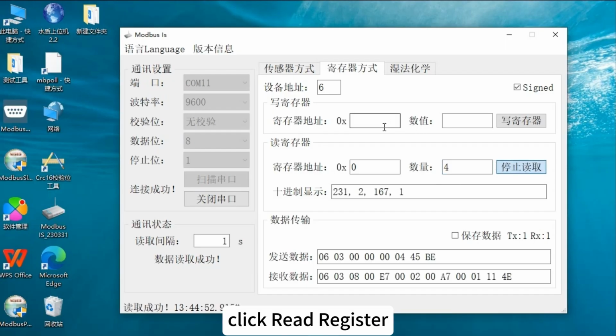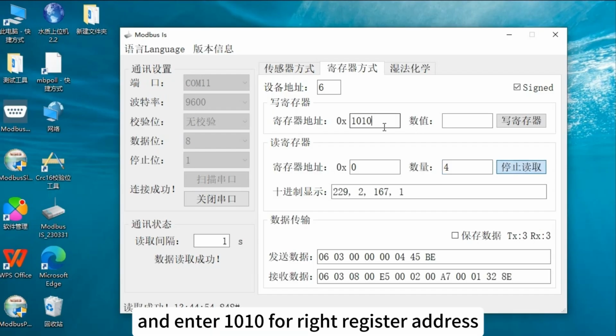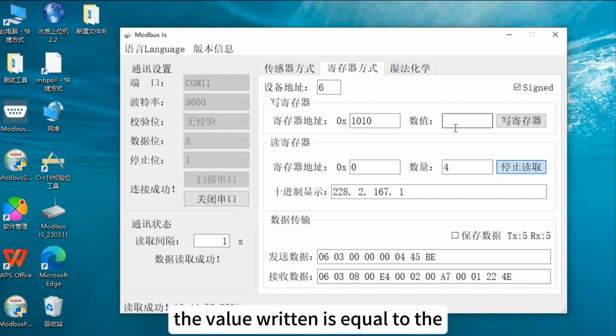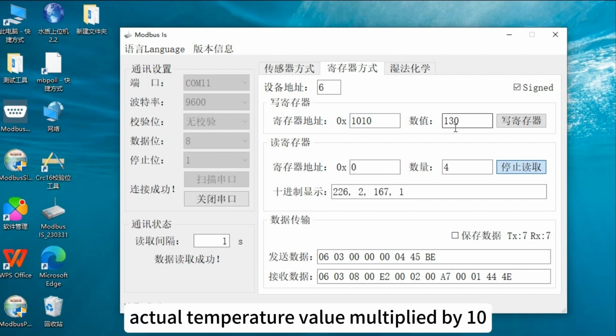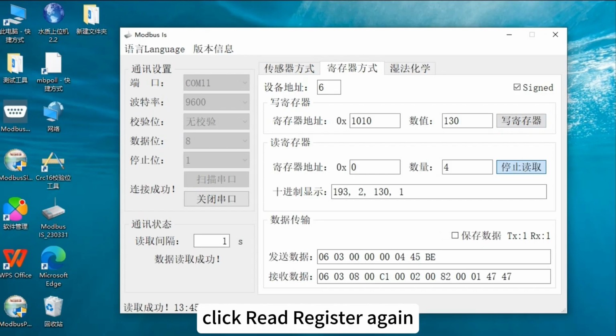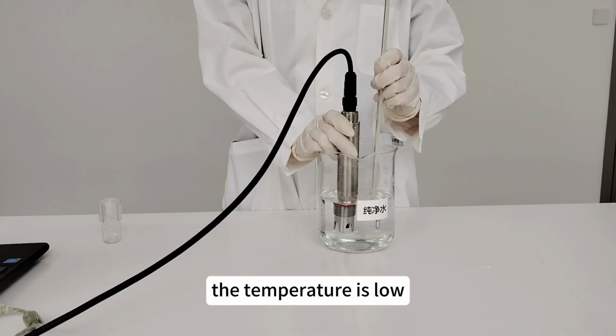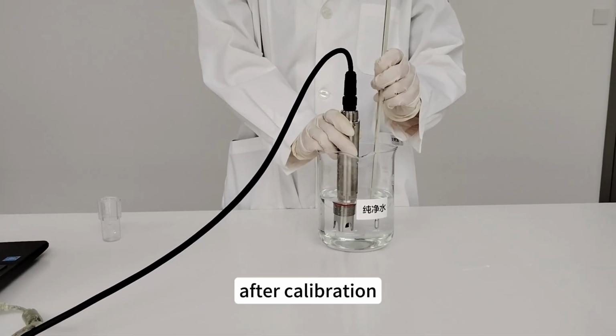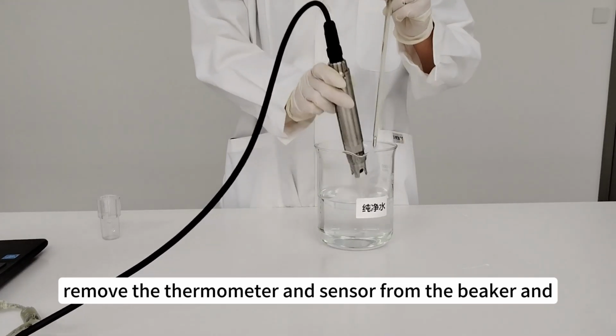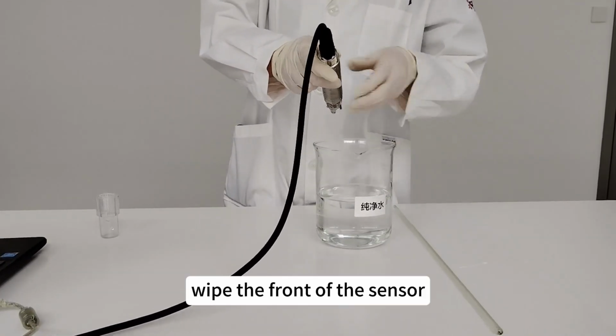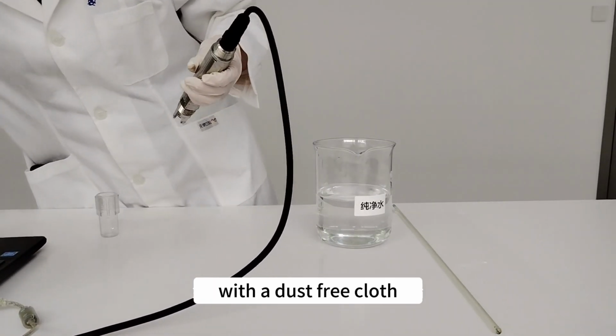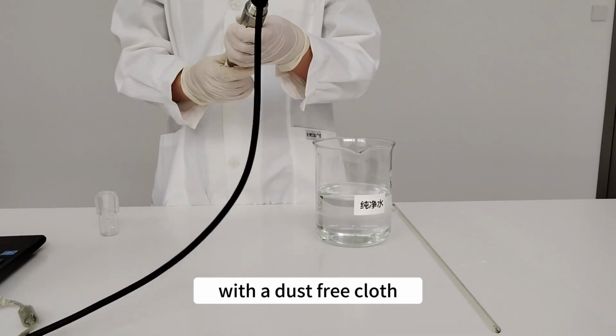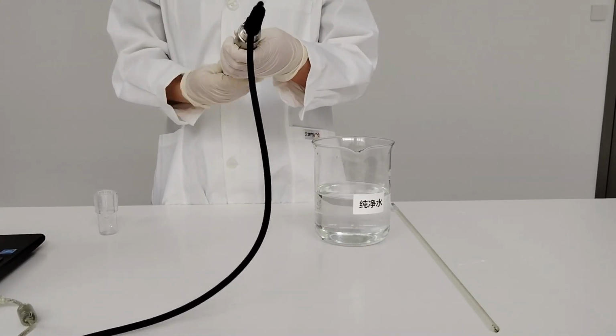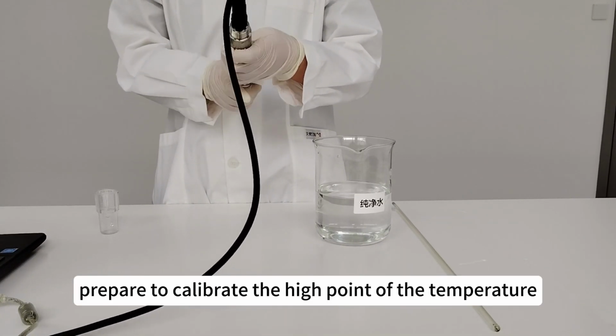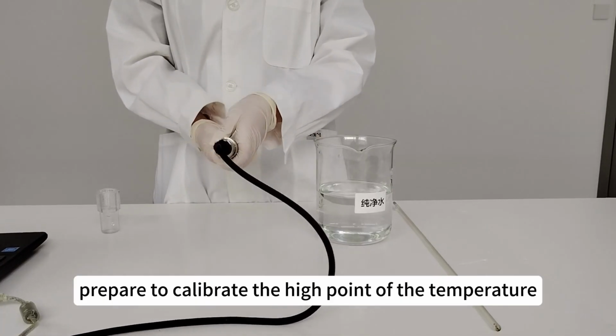Click Read Register and enter 1010 for Write Register Address. The value written is equal to the actual temperature value multiplied by 10. Click Write Register. Click Read Register again. The temperature low point calibration is complete. Remove the thermometer and sensor from the beaker and wipe the front of the sensor with a dust-free cloth. Prepare to calibrate the high point of the temperature.